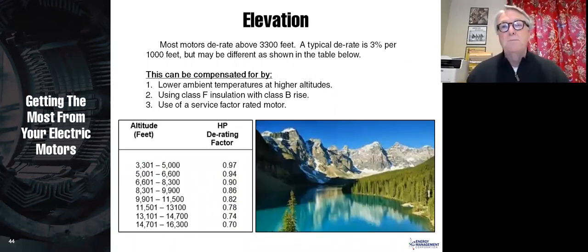Elevation. Most motors you have to derate above 3,300 feet. However, we typically don't. Why don't we? Because many times at higher elevations, you have lower ambient temperatures, and that can compensate. And also, if you use a good motor that has a Class F insulation with a Class B rise, and you use a service factor rated motor, then those things compensate for the derating. And you can see some typical deratings down here. Certainly, if we're up in very, very high elevations of 10, 15,000 feet, then what I just told you probably is not true. But in the lower elevations that we see around here, typically that will compensate.